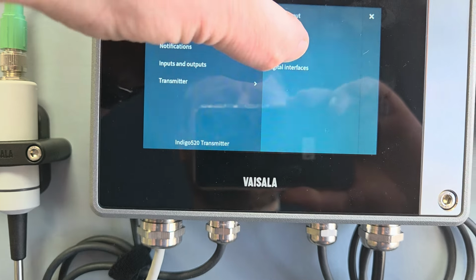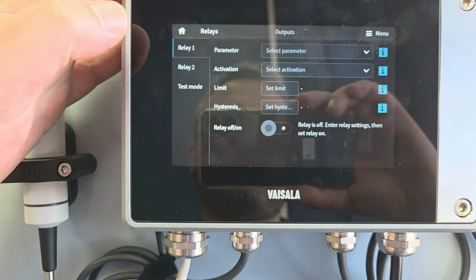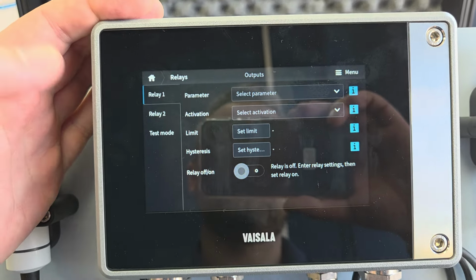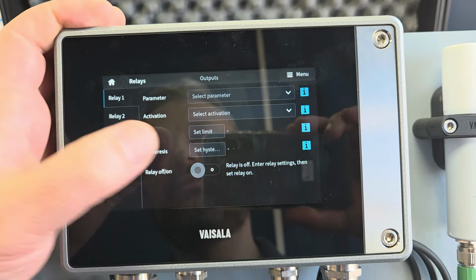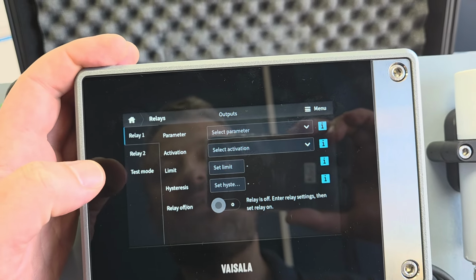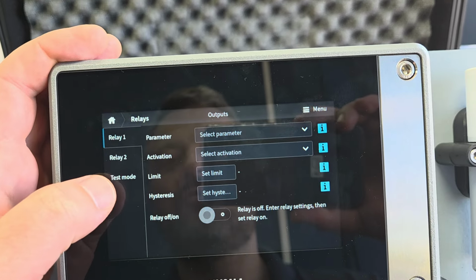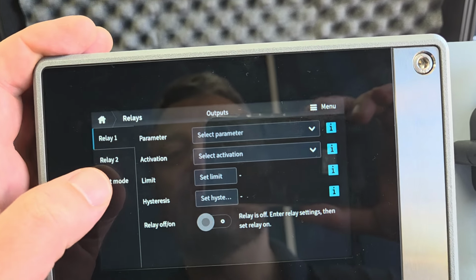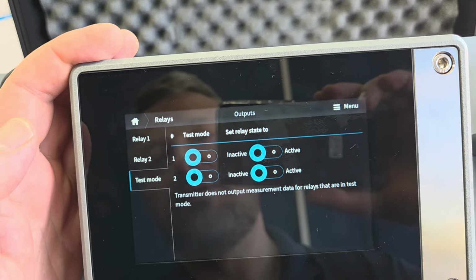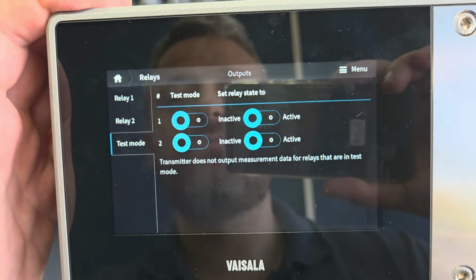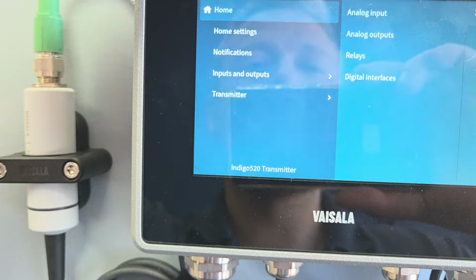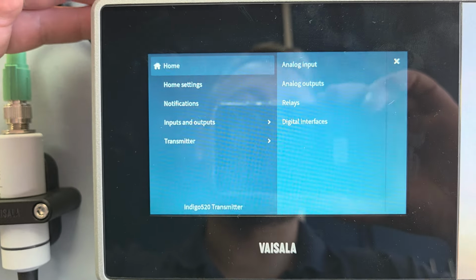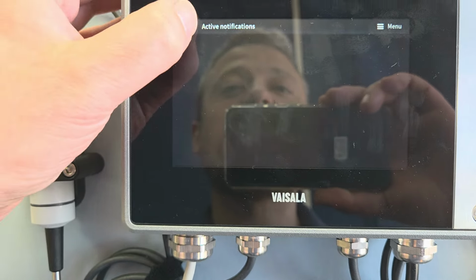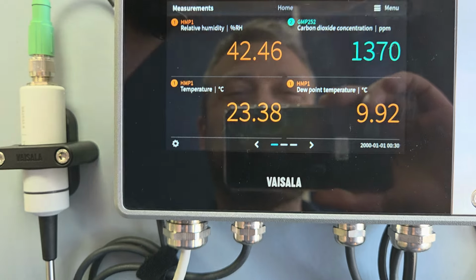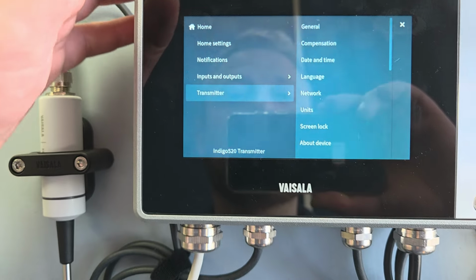Kind of covers the analog outputs and inputs. 2 relays, pretty simple to set up. Hysteresis, like a deadband, I suppose I would call that. Up and down, so you can reduce chattering if you're sitting right on a set point. And again, test points, you could just switch your relays on and off, just prove they're working. Digital interfaces, we can do a bit of Modbus with this. Active notifications, we don't have any problems. That's kind of all you really need to know.